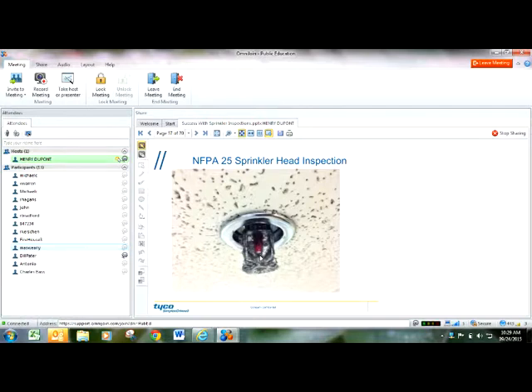So what they've got here, you can tell it's got a fat bulb, it's a semi-recessed chrome standard response sprinkler head, and it's got junk all over it. If you had a blast of compressed air, it would probably knock that off, or you could vacuum that off. But that would be the only means acceptable by code for cleaning a sprinkler head. If you've got paint on any part of the sprinkler head, the arm, the frame, the deflector, the fusible element, it has to be rejected and replaced. The code book doesn't say anything about the escutcheon plate, so I've seen a lot of escutcheons with splashes of sheetrock mud or paint on them. I would consider that okay, but if any of that gets on the sprinkler head itself, it has to be rejected as part of that inspection.